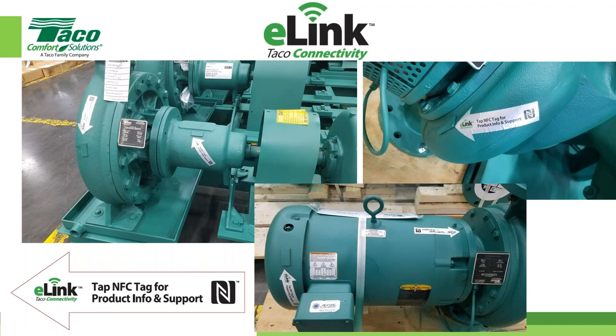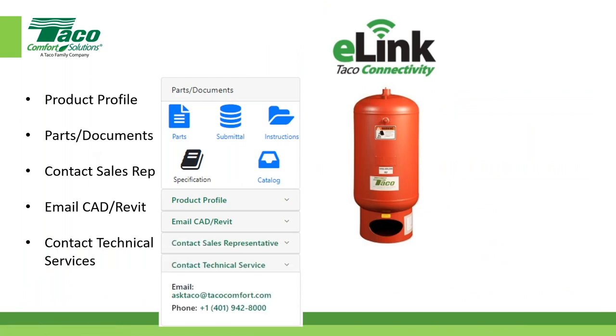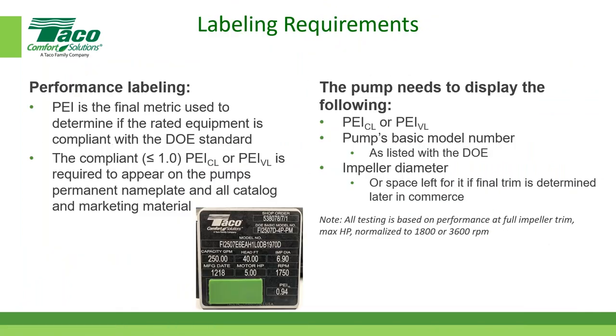But I think not many, but sometimes, especially 10, 12 years into it, this tag that I'm pointing to right now, the pump tag, or what I showed on another screen, may get removed because people want to take that into their office or whatever. So I truly believe, well, maybe I'm just being naive, that there's a better possibility that the TACO eLink tags are going to stay on more so than the one with this information here, because a lot of people won't even know what this is specifically. But unfortunately, they can be taken off.